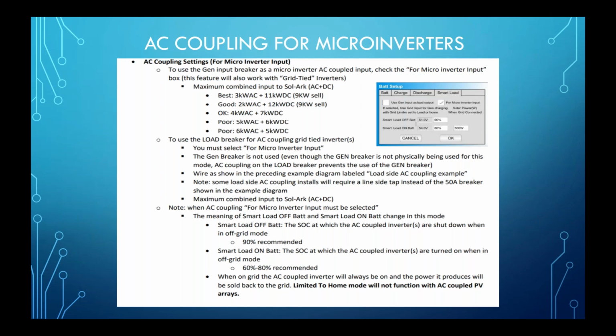Again, there are some rules here about AC and DC coupling. It's best if they're apart from each other, one low on the AC side or DC side. It's less optimal if the two are sitting next to each other, like 5 kilowatts AC, 6 kilowatts DC, or vice versa. It likes them to be one low, one high. The best would be 11 kilowatts DC, 3 kilowatts AC, as it talks about here.